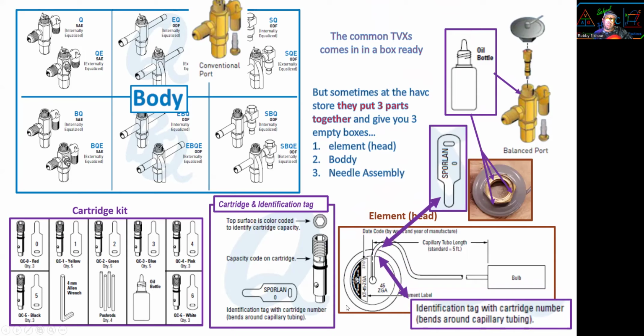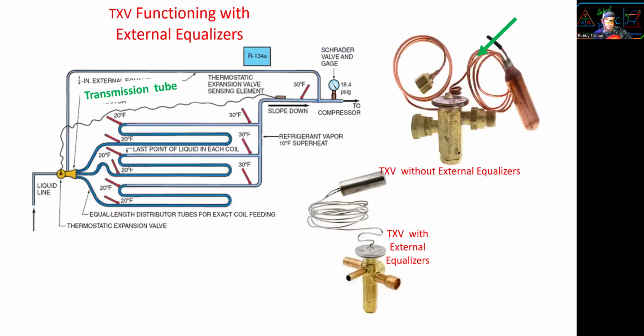So next time I have to replace the valve, they know. The body has a number on it, the head has a number on it. The only thing you cannot see is the cartridge inside. So they put a little tag on the cap tube on the transmission line. I never did it because we technicians don't do it, but people at the parts house do it all the time. Now, let's go back to the function of the external equalizer.